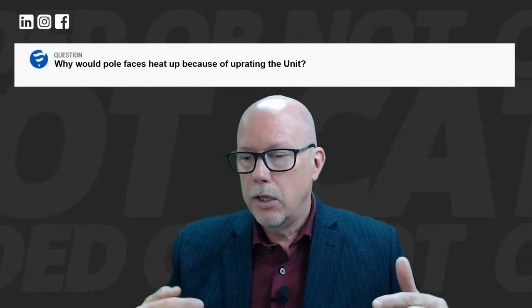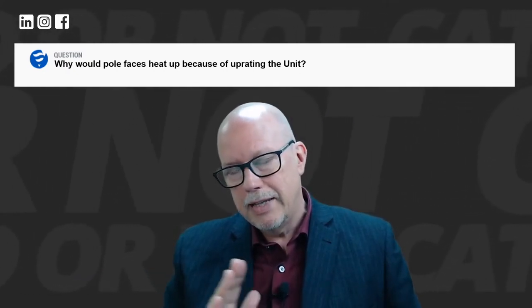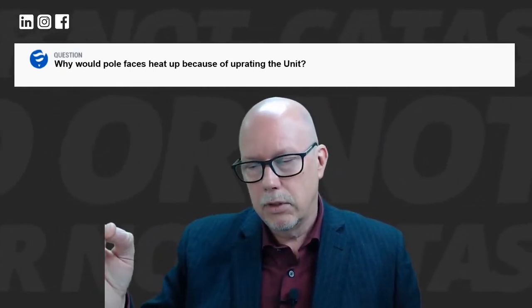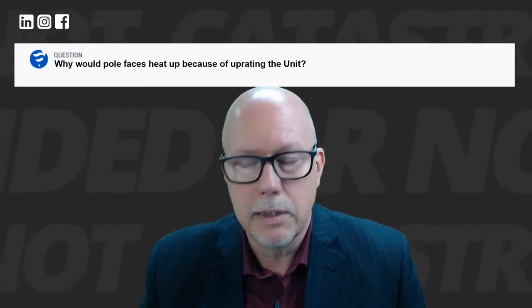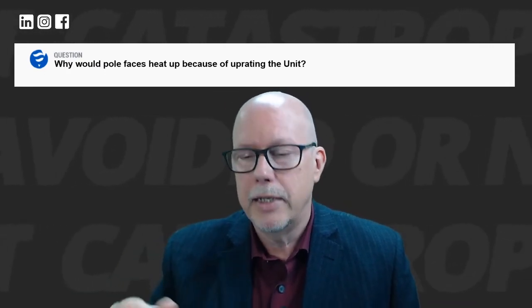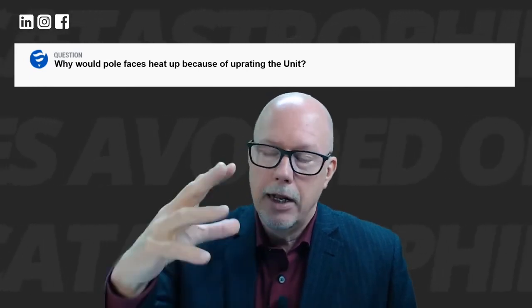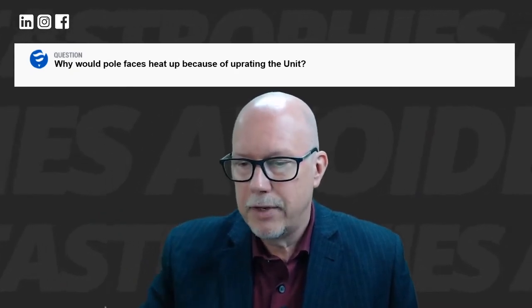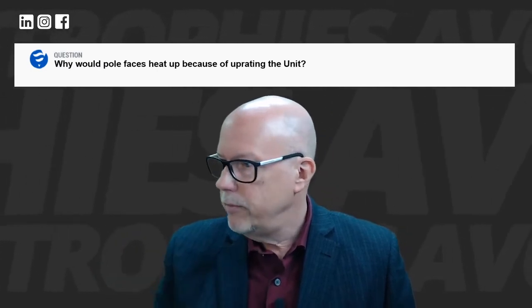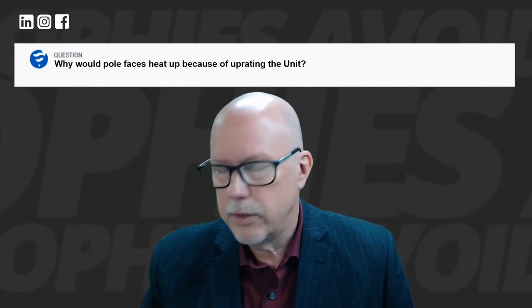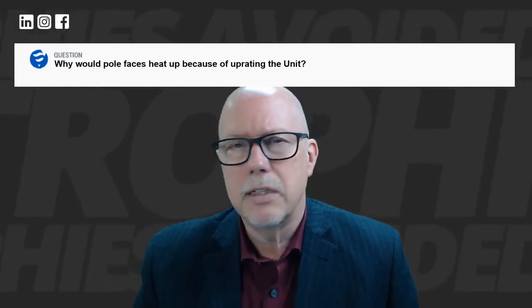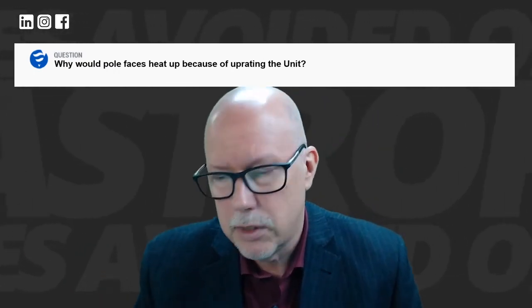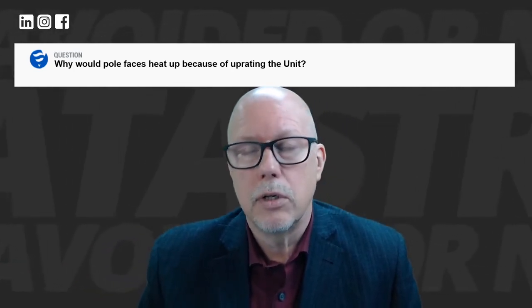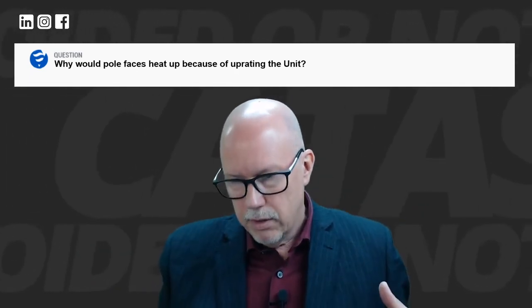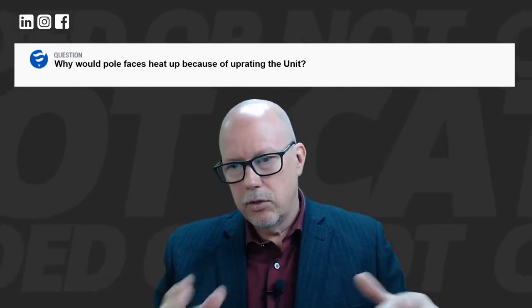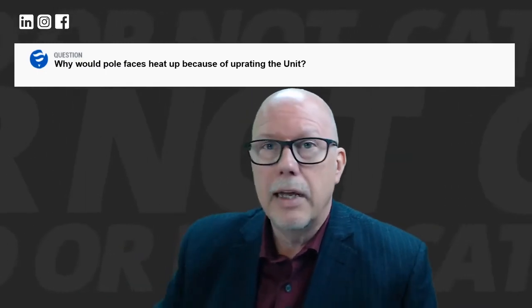Now, if in addition to that you have a stator that's not round, it means each pole, as it rotates, will be subjected not only to a higher level of flux intensity, but a varying level of flux intensity. That variation can create eddy currents in your laminations, and also in the pole faces, and in some cases the amortisseur bars. All of these can heat up way beyond the specifications of the materials you have, and will cause issues. We've been involved in a few cases where they suspected these issues. One was in the Maritimes here in Canada, where they expected to measure something like 65 or 70 degrees C on the pole faces, but we saw levels up to 105 degrees C. So they had uprated the unit and had issues which we were able to document. Increased electromagnetic strength, in addition to incorrect symmetry between the rotor and stator, can and will produce excessive heat on the pole faces and other components of the rotor as well.